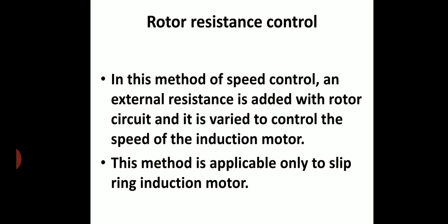Rotor resistance control. In this method, an external resistance is added to the rotor circuit and it is varied to control the speed of the induction motor. This method is applicable only to slip ring induction motors.